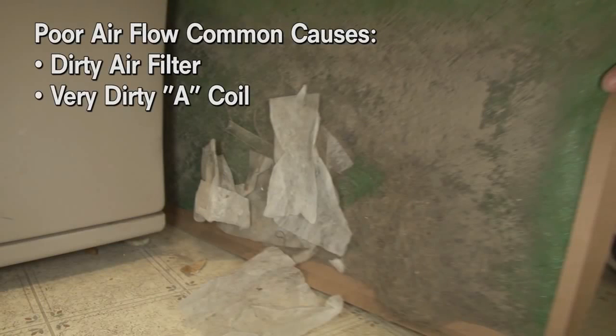Poor airflow, common causes: dirty air filter or a very dirty A-coil. 95% of service calls for air conditioning are because of the filter. If your filter was the problem, congratulations, you just saved yourself a ton of money. If it wasn't, watch on.